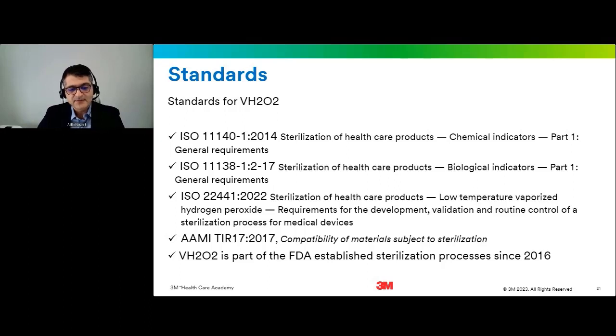So let's look at some of the global standards that apply to hydrogen peroxide processes. ISO 11140 Part 1, Sterilization of Healthcare Products: Chemical Indicators, mentions the general requirements for the chemical indicator types. ISO 11138 Part 1 mentions the general requirements for biological indicators. ISO 22441, which was published last year, is a new document which discusses the requirements for development, validation, and routine control of a sterilization process for medical devices.